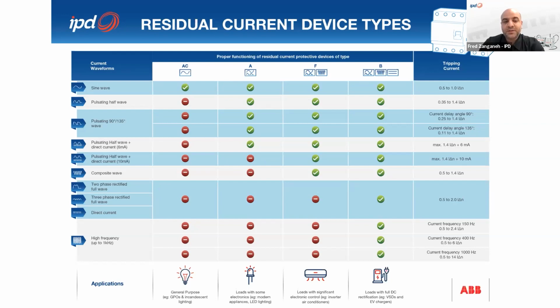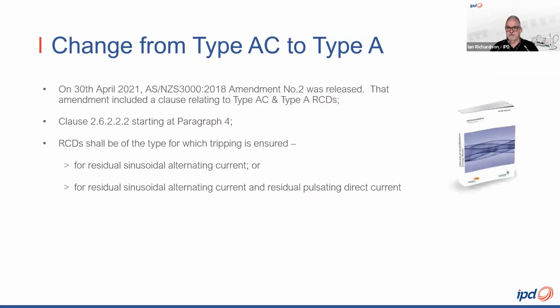Yeah, also the types that you mentioned in this table match the RCD types described in the Wiring Rules, AS/NZS 3000 as well. Absolutely. And Fred, I'm glad you brought up the wiring rules. The Wiring Rules Committee and the safety regulators have noted that there's been a shift in the appliances and loads that can generate different earth fault wave shapes. So on the 30th of April 2021, Amendment number 2 of the Wiring Rules was released. That amendment, as we know, included a clause relating to type AC and type A RCDs.